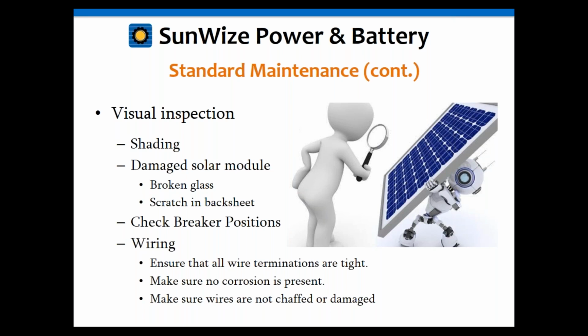A damaged solar module could be damaged because something has hit it, that could be vandalism, or it could have been hail that has broken the front glass, or the back of it may have gotten damaged somehow by wildlife. We frequently hear about rodents gnawing on the back of them as well. So that's just something you want to check for and either repair or replace. You want to check your circuit breakers, make certain that they are all good and functioning well. And wiring, I mentioned that before. You want to definitely check for corrosion. Make certain all the connections are tight. That's where the screwdriver comes in handy, especially if you have a junction box in the back of a solar module.